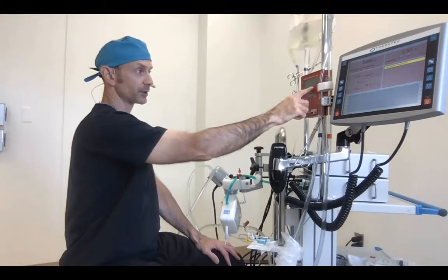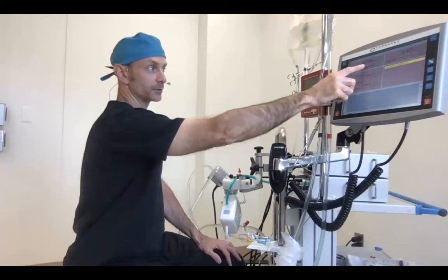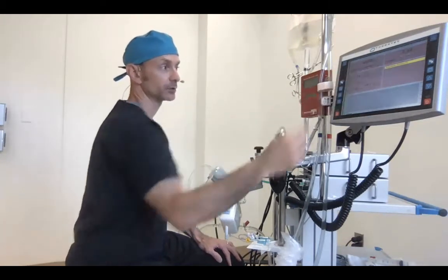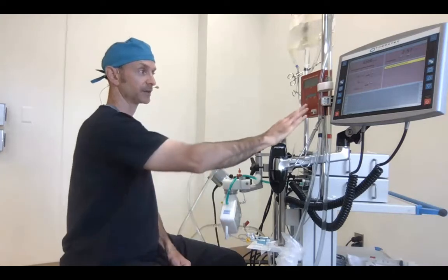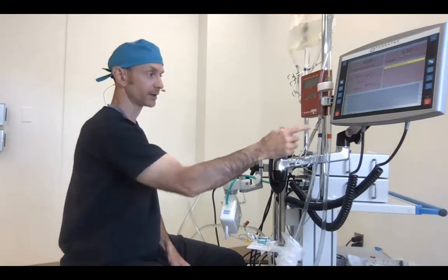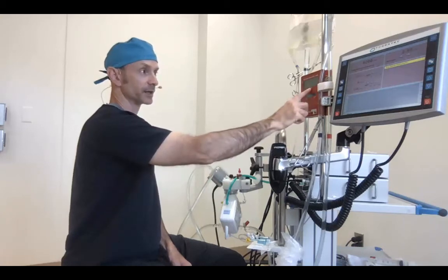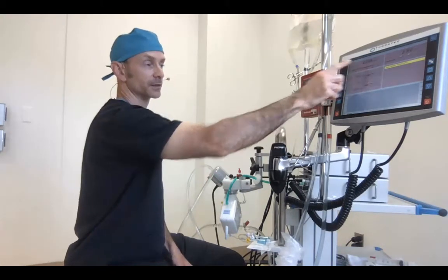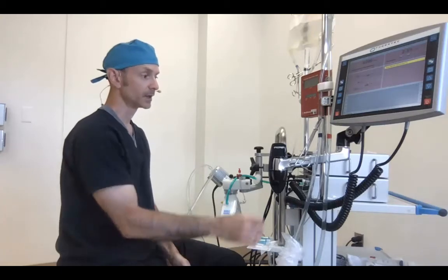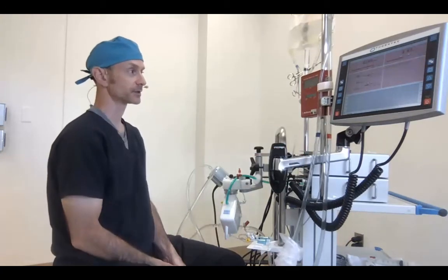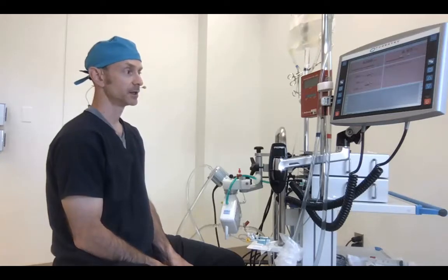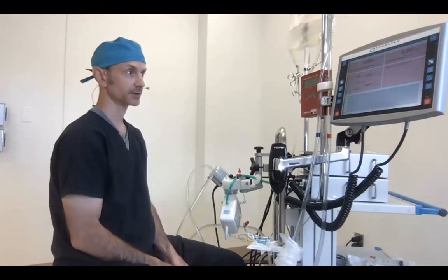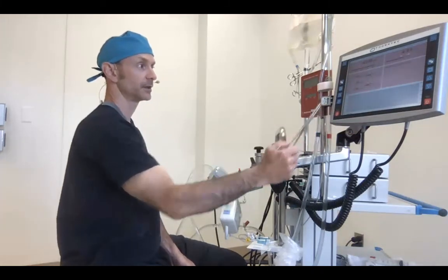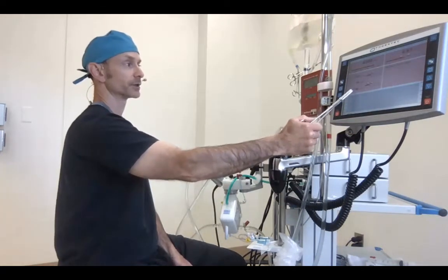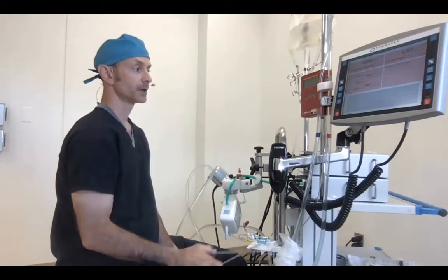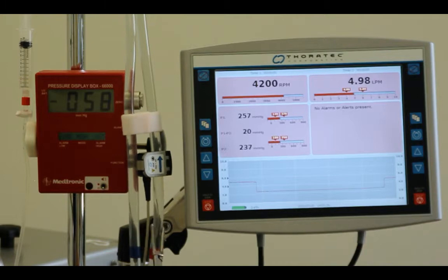But the venous line pressure is more negative. At the same RPMs, we generate a more negative pressure and get lower flow. So this is a clear indication, if you have a venous line pressure, that you have a preload problem, when this becomes more negative and the flow comes down at the same RPMs. Let's relieve that and go back to our baseline status here. And we see that without any additional resistance, we're at 5 liters, 250, 230 or 240-ish, and -50 over here. Now let's add some resistance to the arterial side.